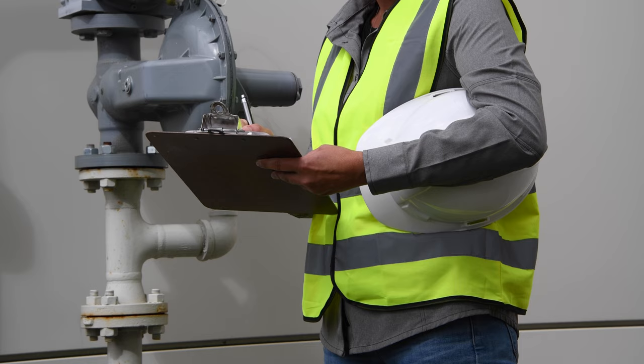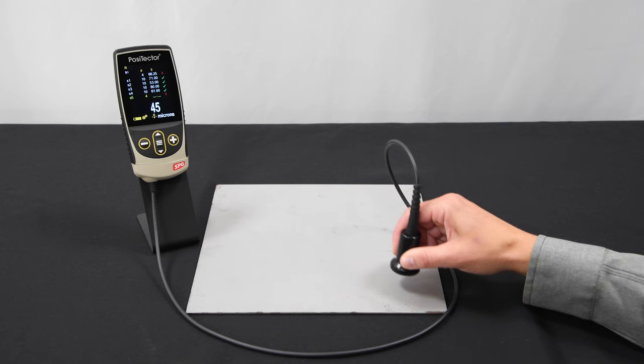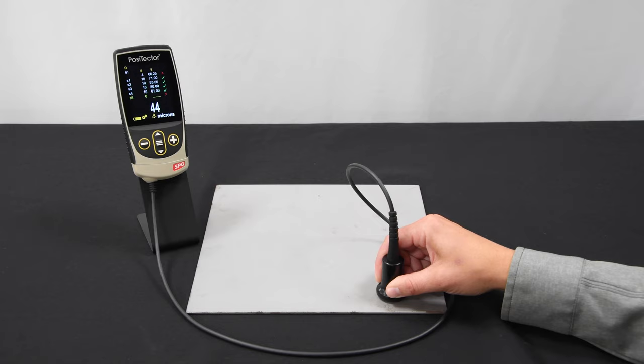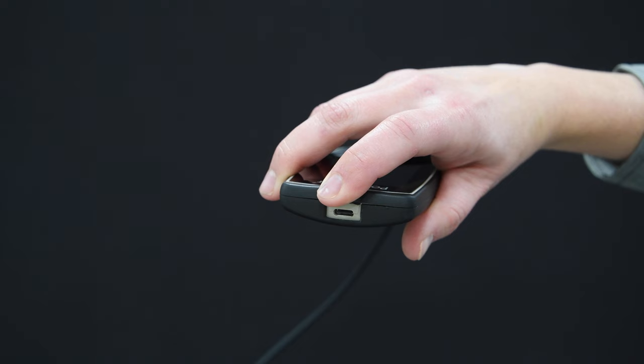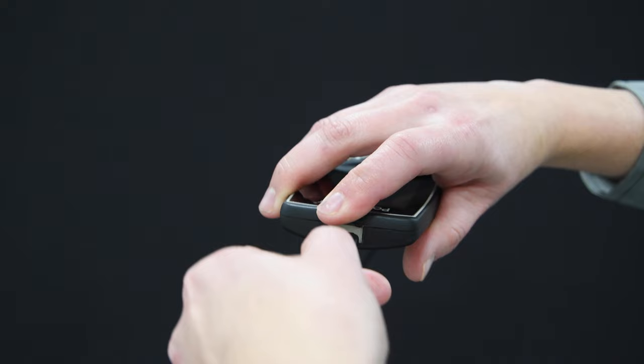On competitive instruments, this method is challenging to follow and requires writing down many readings. PosiTector SPG advanced models feature smart batch, making this process easy by automatically keeping only the highest reading in each spot and averaging several spots together right on the gauge.